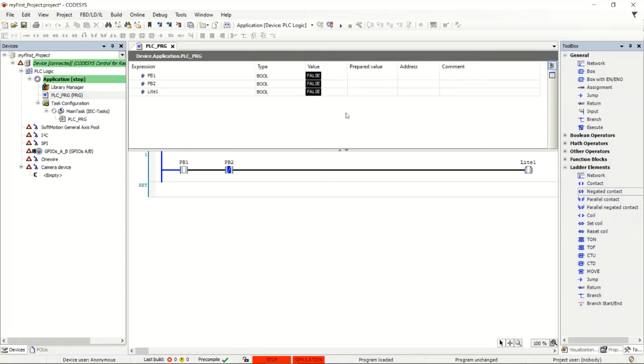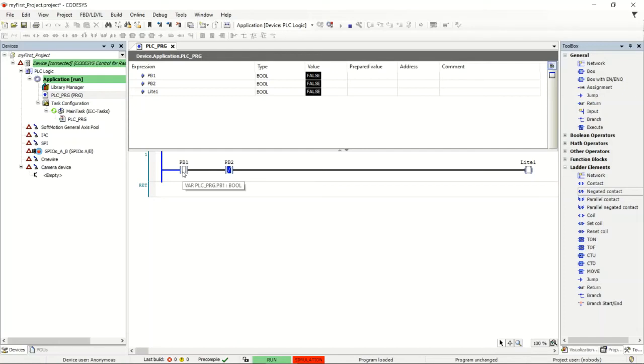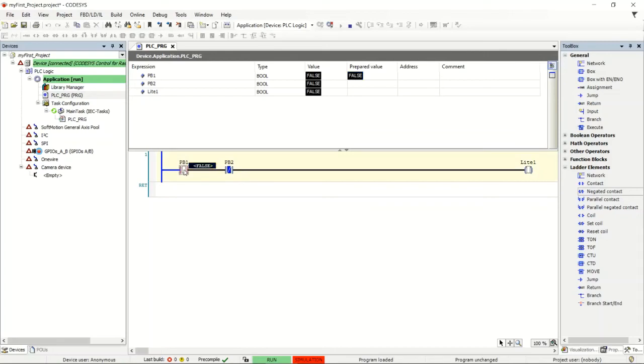Let's run this program. Up at the top there is the Start or Play button. Hit Start and it puts the project in Run — your simulated PLC is now in Run. It's processing its logic right now. Since there's nothing writing to PB1 from real IO or anything else in the program, I can actually toggle it. To toggle it, I highlight the instruction and double-click it — it sets it true. Double-click again and it sets it false.